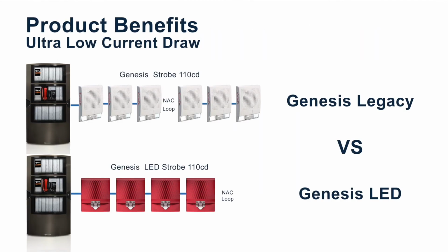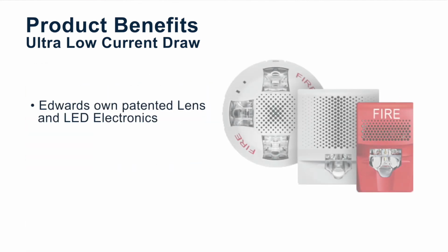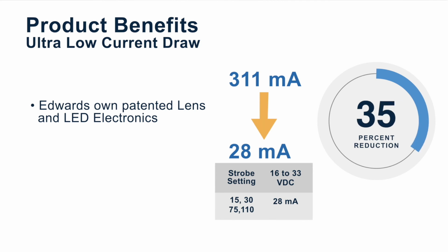Ultra-low current draw is one of the most exciting features in the Genesis LED line. Using an LED in place of a xenon bulb will reduce current draw. But since they are normally power hogs, notification devices needed a drastic reduction in power to make them easier to deploy. With patented lens and electronics, Edwards was able to drop the current draw on a 110 candela strobe from 311 milliamps to just 28 milliamps. That's over a 90% reduction in power.